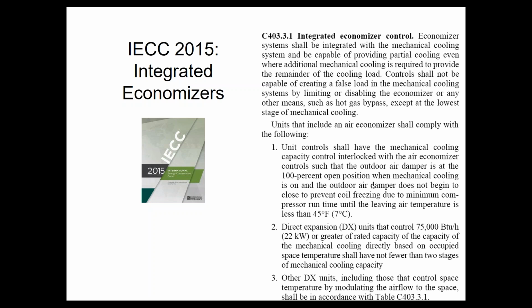So if you're designing for 55 degrees, Andy, then your statement is true. You need to be able to get down to 55 degrees with the economizer itself. If your design for some reason was 58 degrees supply air, then I guess you'd only have to get down to that with the economizer.